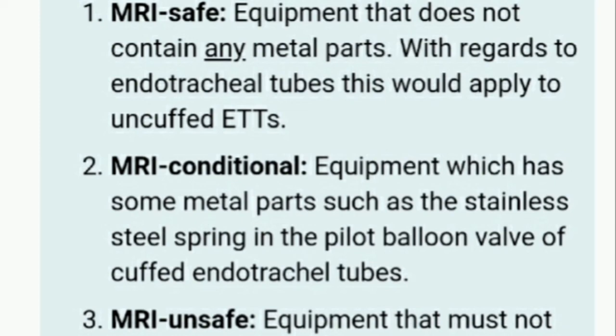It might still be worth avoiding using armored tubes in the MRI environment as the metal coil can adversely affect picture quality, especially if the scanned area is in close vicinity to the tube, that is in the cervical spine and brain MRIs.